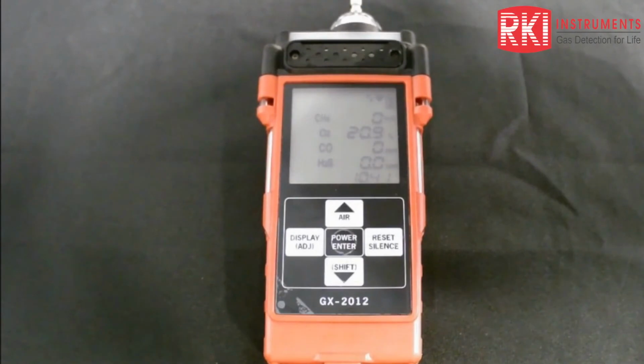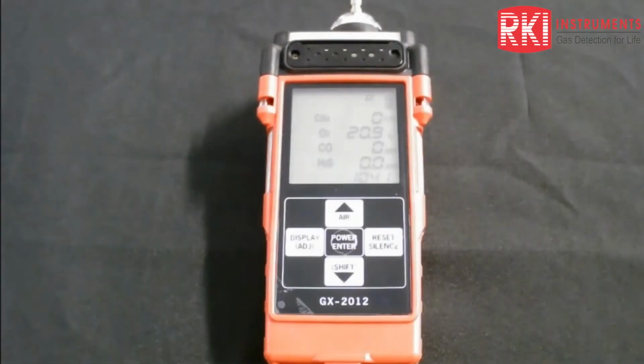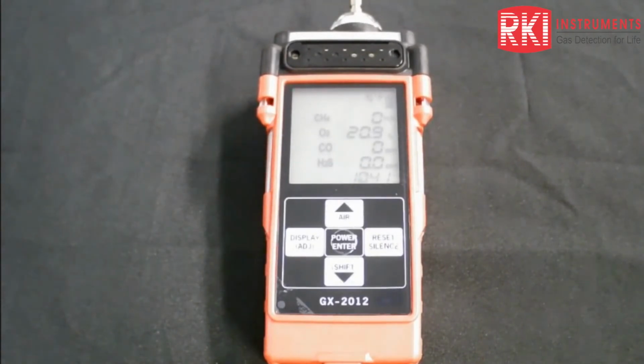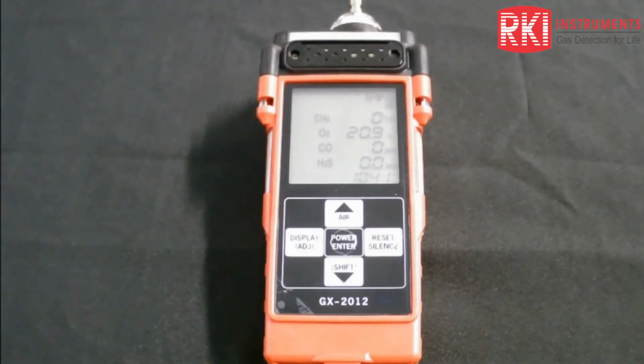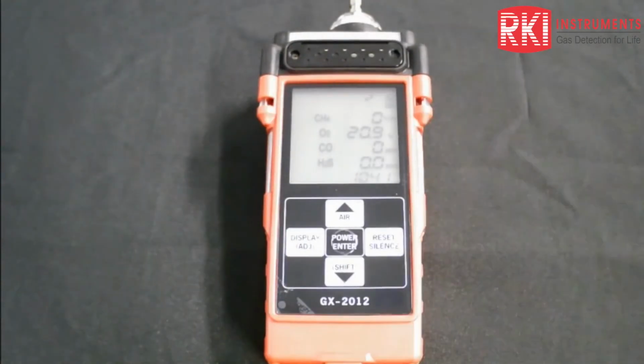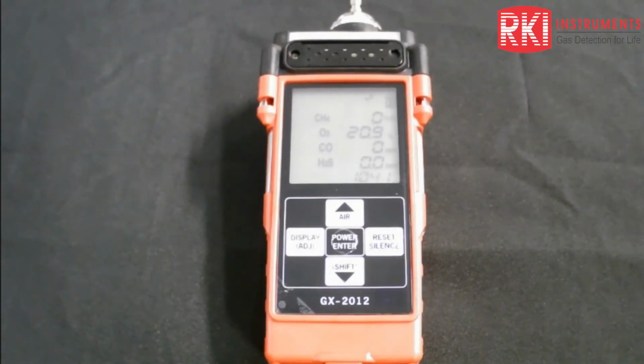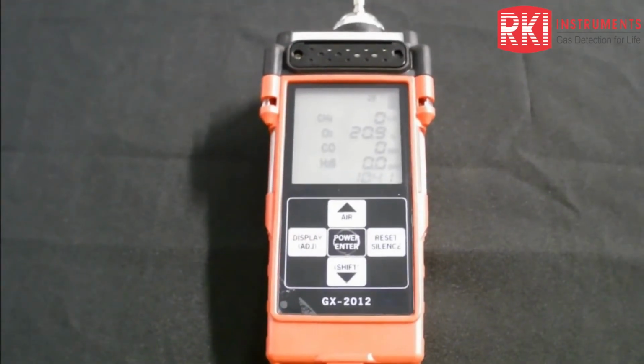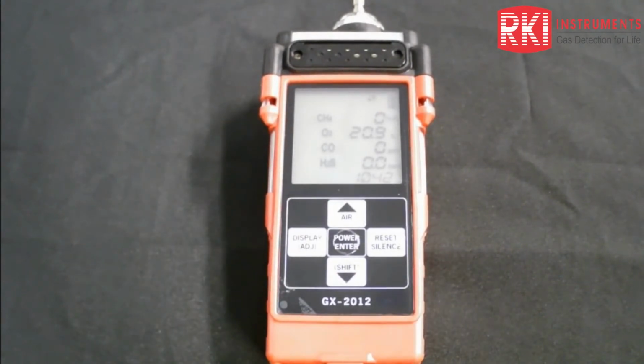You could make that choice by using that display key function to say, hey guys, I know that I'm going to be working in high concentrations of gas. I would like to prevent my LEL catalytic bead sensor from burning hot. And when you do that, you preserve it because you're not going to be burning the catalyst off of it. Right. So oftentimes when I speak to people about my equipment, I'll hear what happens to their equipment presently, and that is, hey, John, we keep going through a lot of LEL sensors. I don't understand why. Well, the reason is they keep exposing those LEL sensors to high concentrations of percent by volume gas, and they're just burning the catalyst off very quickly.